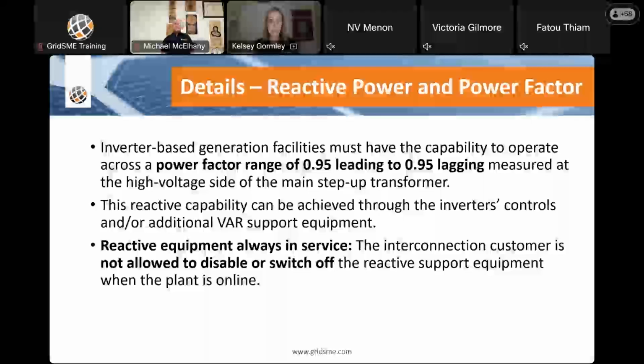So in very basic terms, the plant should be able to both supply reactive power leading and absorb reactive power lagging up to roughly 33% of its real power capacity to support grid voltage as needed. So this reactive capability can be achieved through the inverter's controls or additional VAR support equipment. Modern inverters are designed to provide reactive power within that range. However, if they don't, the interconnection may require installing supplementary devices such as a shunt cap bank, reactors, things like that to meet that VAR range.